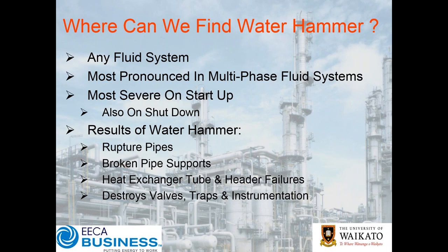For example, if you have condensate in a steam system being condensed from steam in a heat exchanger, that condensate will actually be saturated — it will be at the saturation temperature — meaning that any slight changes can cause some of that condensate to flash. Especially after a steam trap, some of that condensate will flash, meaning you've still got a saturated mixture but at a lower temperature corresponding to the lower pressure. The key thing with these saturated multi-phase fluid systems is that fluid can change phase very quickly from liquid to vapor phase, and when it does that it can be quite explosive.